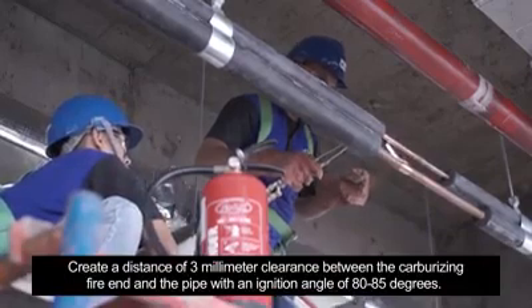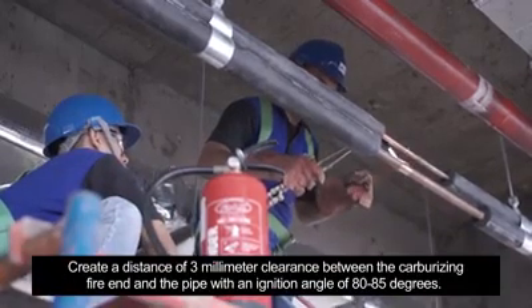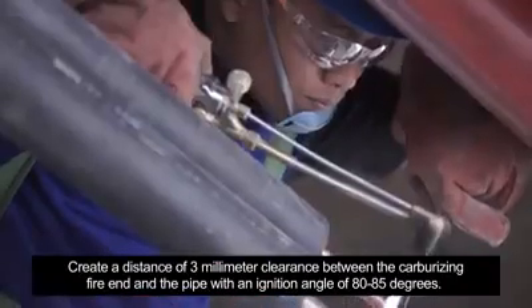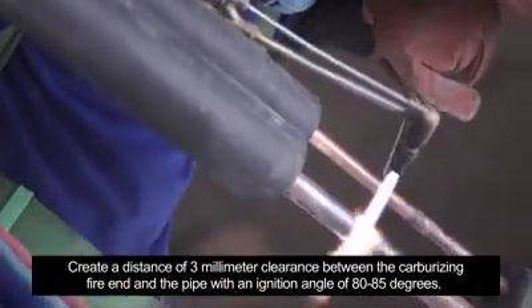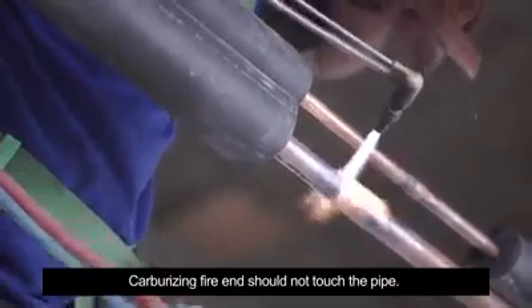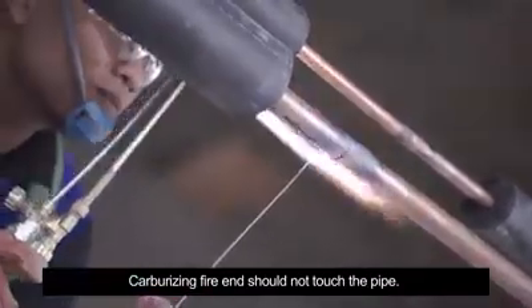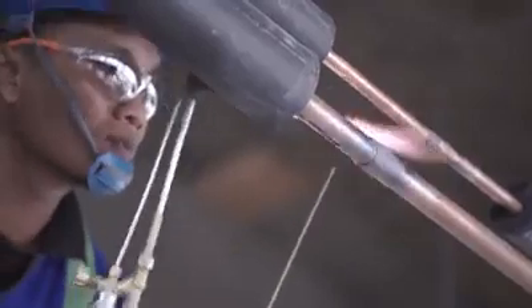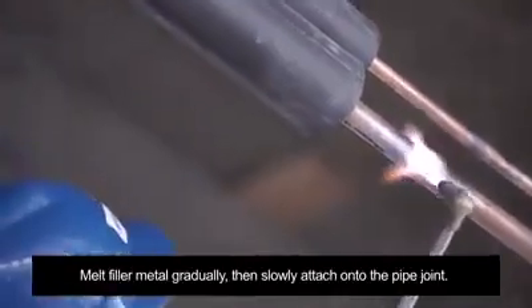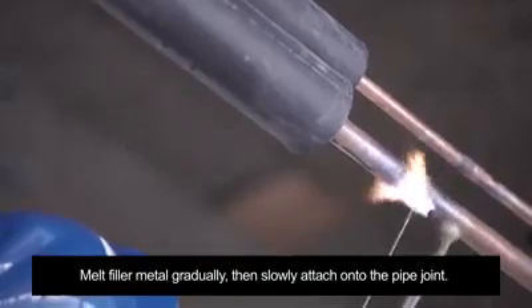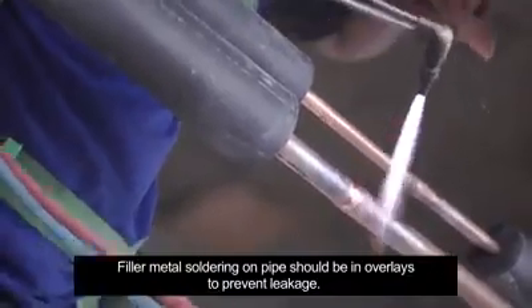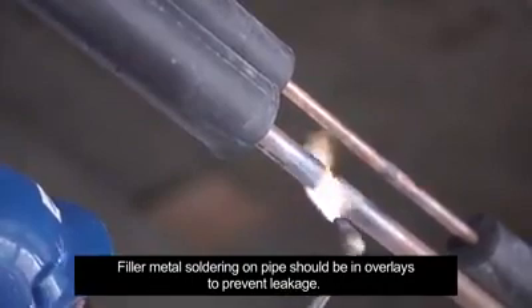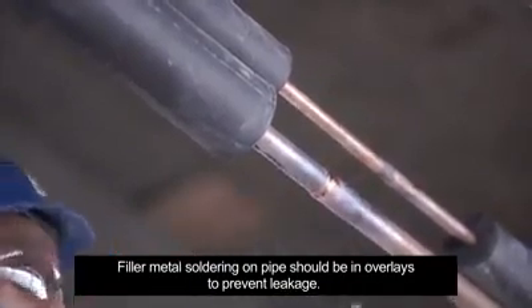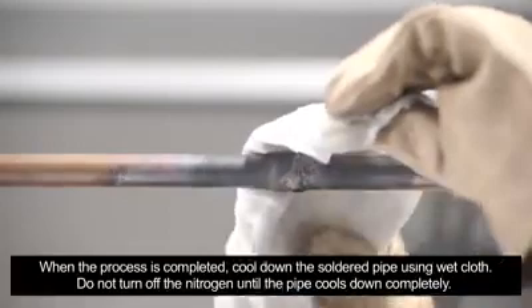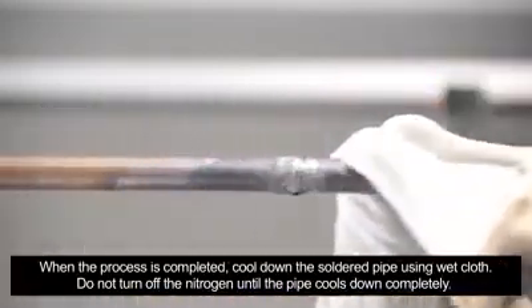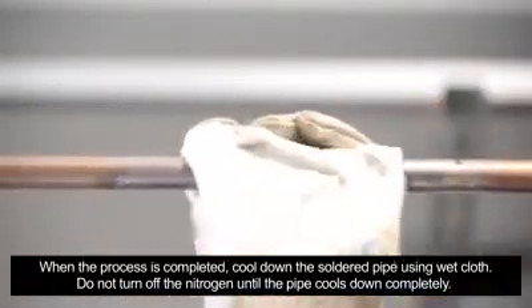Create a distance of 3 mm clearance between the carburizing fire end and the pipe with an ignition angle of 80 to 85 degrees. Carburizing fire end should not touch the pipe. Melt filler metal gradually, then slowly attach onto the pipe joint. Filler metal soldering on pipe should be in overlays to prevent leakage. When the process is completed, cool down the soldered pipe using wet cloth. Do not turn off the nitrogen until the pipe cools down completely.